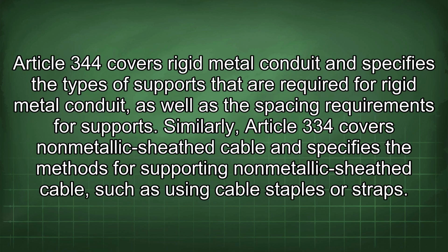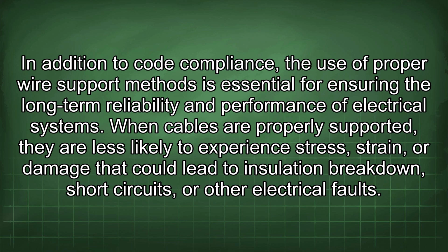Article 344 covers rigid metal conduit and specifies the types of supports that are required for rigid metal conduit, as well as the spacing requirements for supports. Similarly, Article 334 covers non-metallic sheath cable and specifies the methods for supporting non-metallic sheath cable, such as using cable staples or straps.